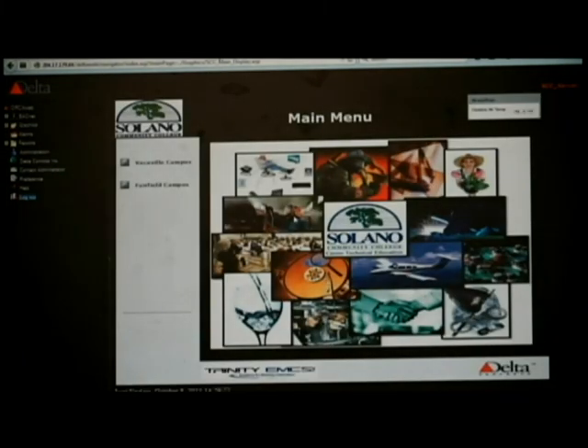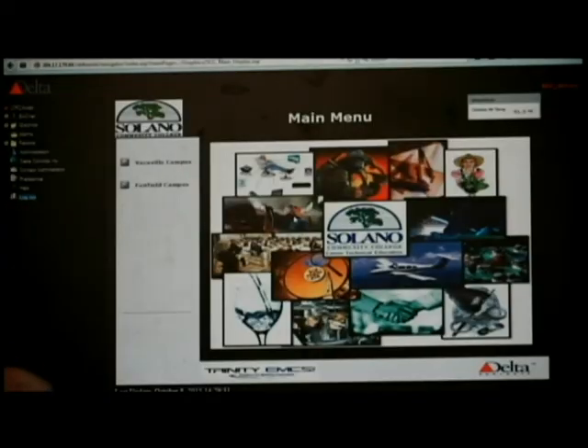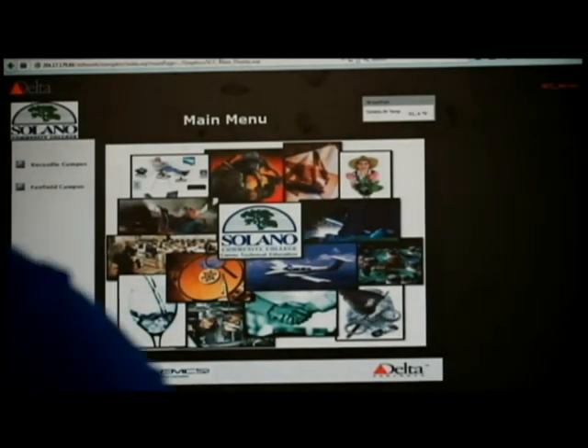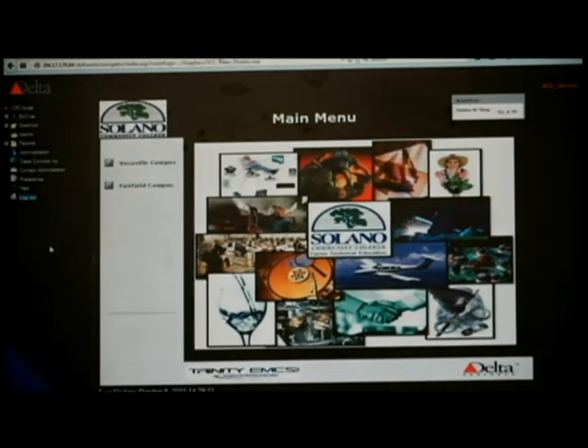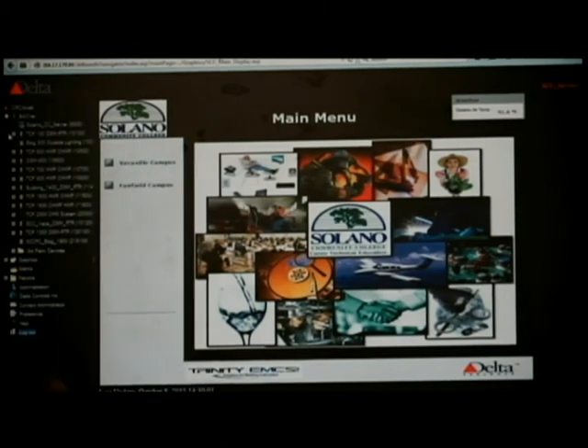So once we log in, we get to the central main graphic because there are several different campuses here for Solano Community College. Currently, on the Delta BACnet system, we run Vacaville campus and Fairfield right now, which you can see are a couple options there. My screen may look a little different than yours depending on the user level account that's assigned or how you want to view things. Sometimes all you're going to see when you log on is a graphic just like that. Mine, this Trinity Tech level one, has these extra options over here where we are able to get down into each device that is on the network and make any adjustments directly there and write and change code inside of those controllers without having to go through the graphics to get to those.